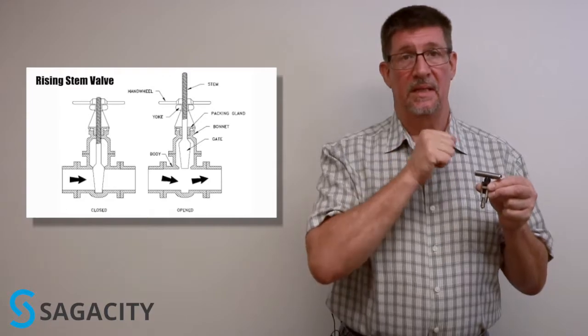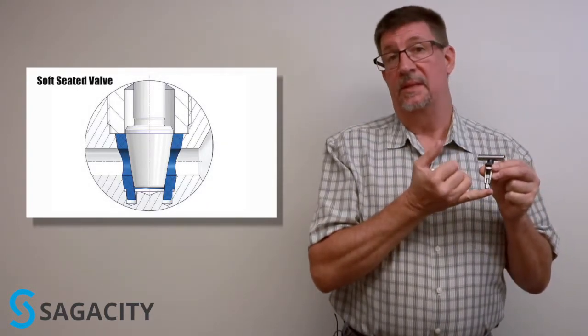They also have a rising stem valve in which the needle itself is actually a V-shape and sits in the seat of the valve. In gas applications, you'll use a soft-seated valve, and the seat material is in the base of the body, and that's where the needle sits.